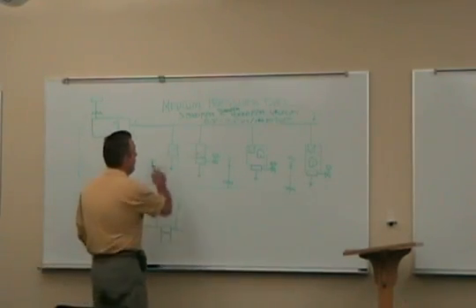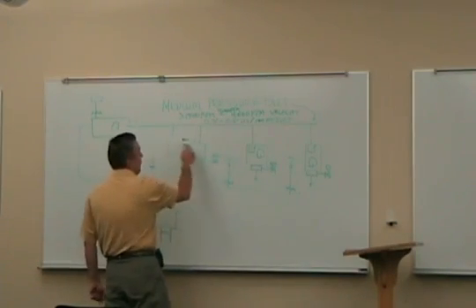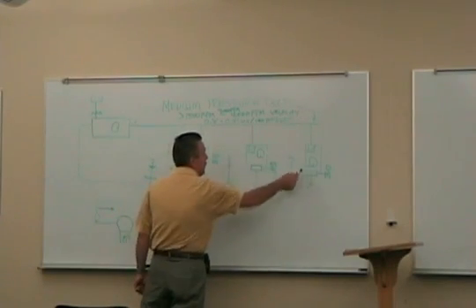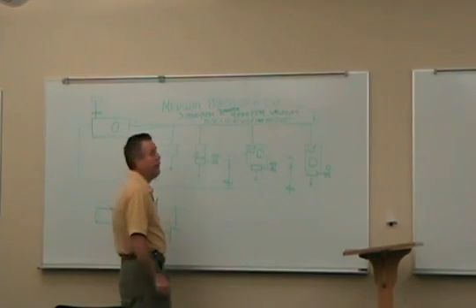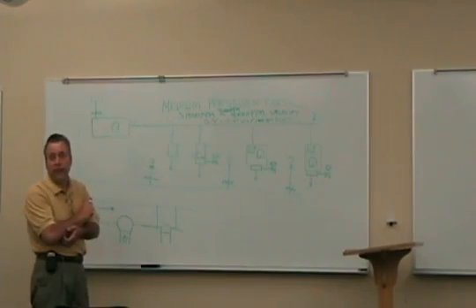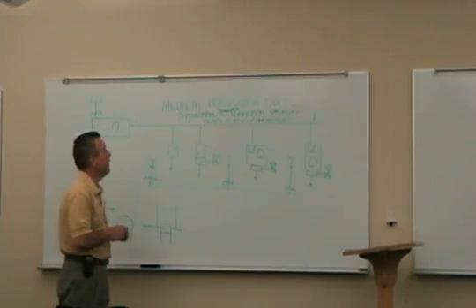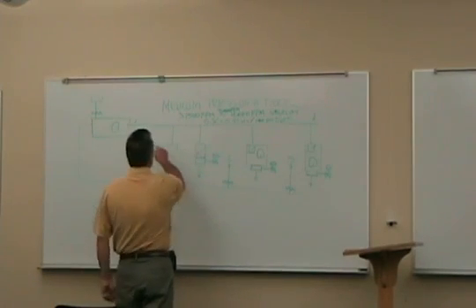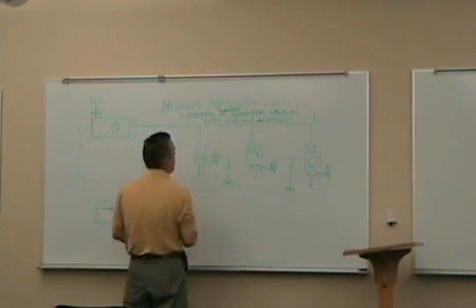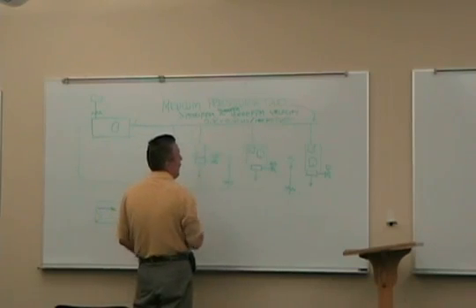You may have a building like this that may be multi-stories. Each one of these is a story. And this floor works fine, can't get any air on this floor, and this floor works fine. And you generally trace it down to some kind of fitting in the duct that causes that pressure drop. It was constructed wrong, it was built wrong, designed wrong, whatever. But the supply duct in a VAV single duct application would be called medium pressure duct. These are the pressure ranges that you size it by.